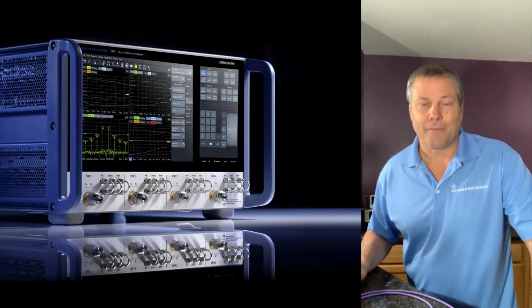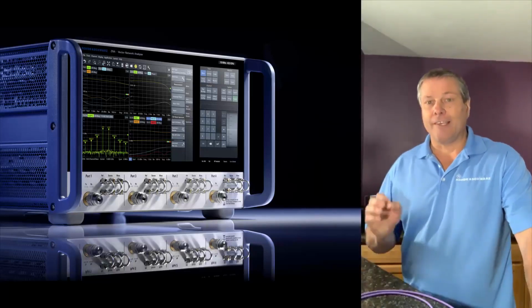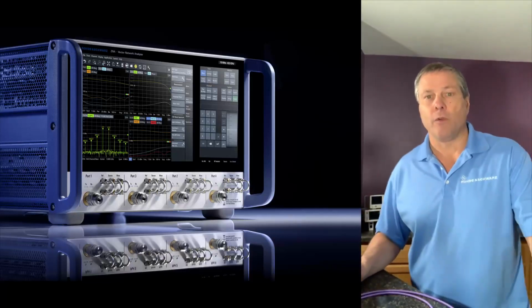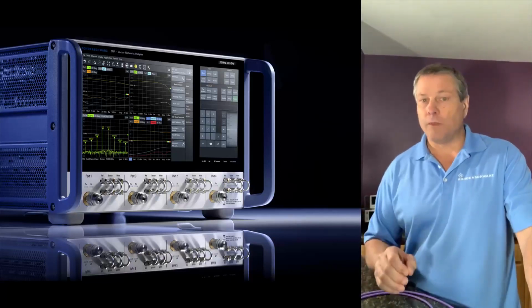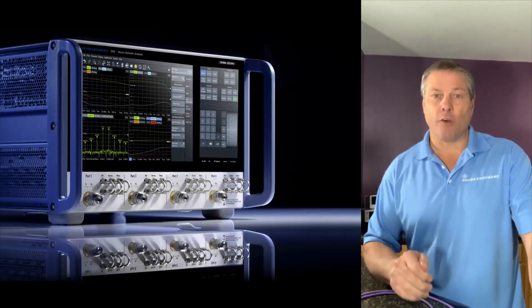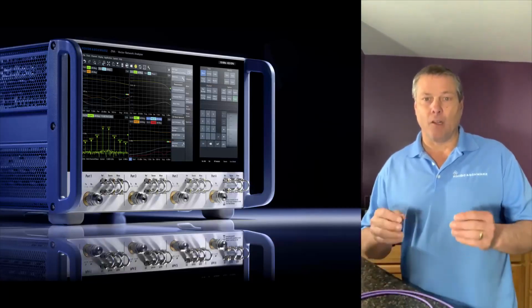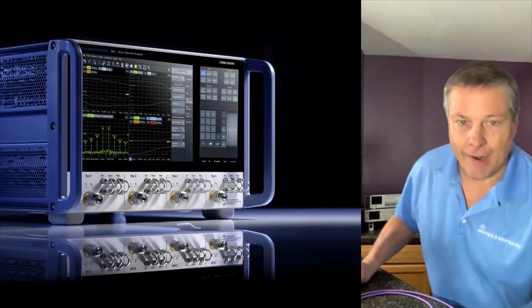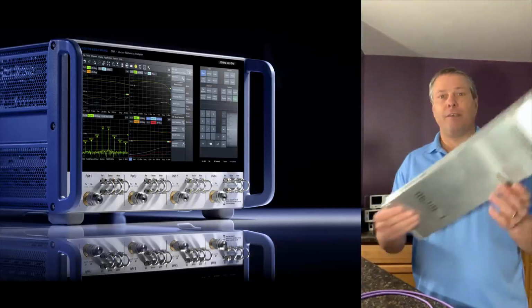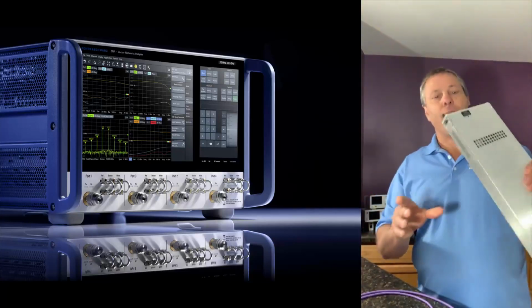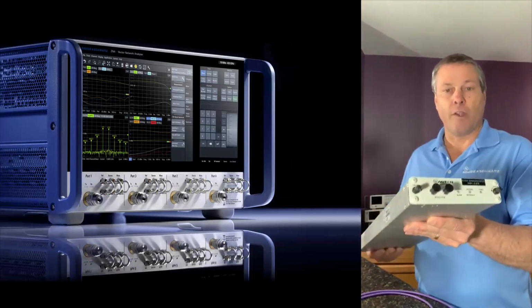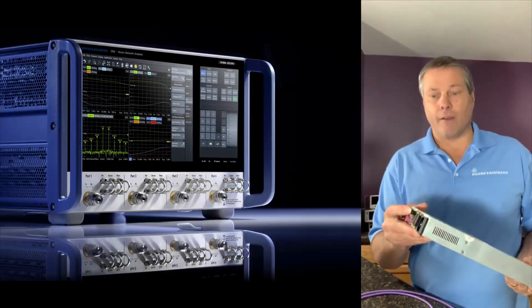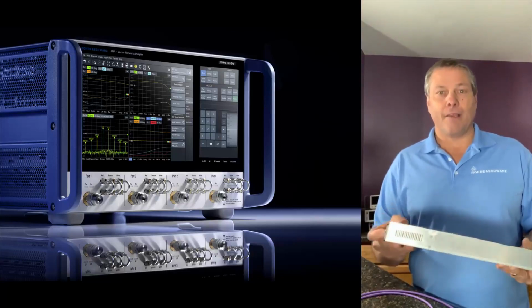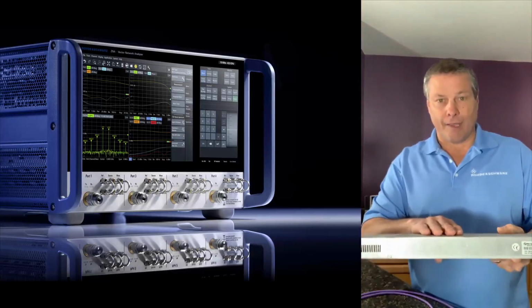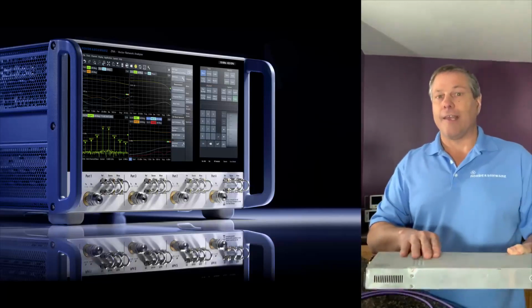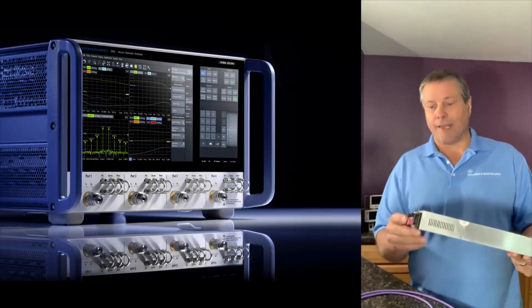Hello everyone, my name is Mike and I have 10 techniques that I'm going to share with you for improving your group delay measurements on frequency converting devices that have an embedded local oscillator. And by that, I mean devices similar to this MyTech satellite block down converter, which is a device that takes a 20 gigahertz signal in on the back, uses an embedded local oscillator running at 18.75 gigahertz, and down converts the signal to about 1 gigahertz at the output.